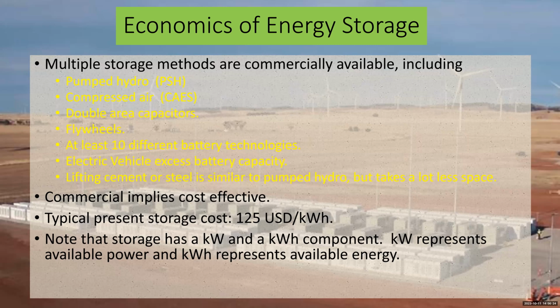Storage is an interesting thing, because when you say you've got, I'm sorry, when you say you have 129 megawatt hours of storage, that's kind of misleading, because you can, depending on your rate of discharge, discharge all 129 of those in a day's time, which is the so-called C over 24 discharge rate, which you can do with anything. That means you can fill them up again the next day and do it again, 365 days a year. So that's that many megawatt hours per day of being able to store and give back again, and that's something that is not necessarily realized.